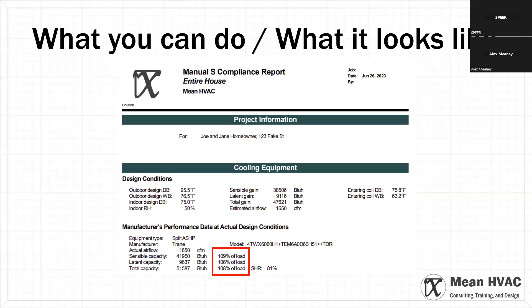I believe we need to be more aware of the spirit of the law versus the letter of the law. If you strictly apply that 15% sizing limit, you can end up in a range where a 1.5 ton unit won't do the job, it's too small, but a 2 ton is technically too big. There's a huge range here, and these are drawn to scale, for the record, showing the differences between sizes at smaller tonnages.